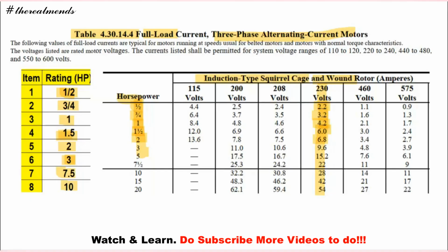Pag 3 HP, we have 9.6. 7.5 HP, we have 22. So pag 10 HP, meron tayong 28 amperes. So itong value na to sa table, ilagay natin dun sa ating schedule.